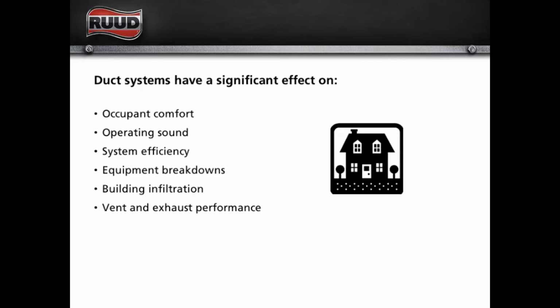Also, the higher your static is and the more air you're moving through your ductwork, the higher the likelihood is that you're going to rattle the registers and/or grills. Sometimes it can be really loud. If you've ever had a customer complain that it sounds like a truck is coming through their ductwork, you might have some airflow issues.